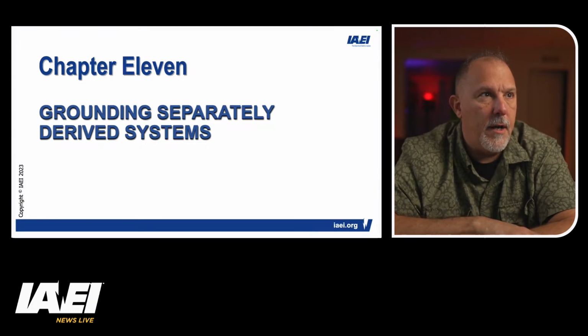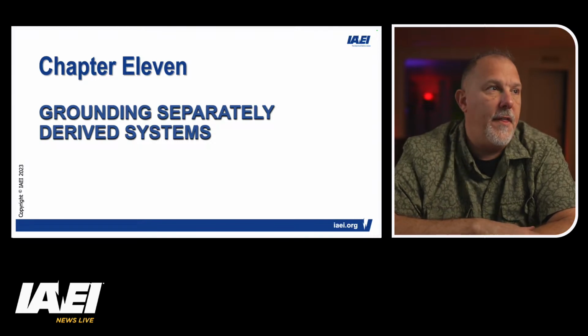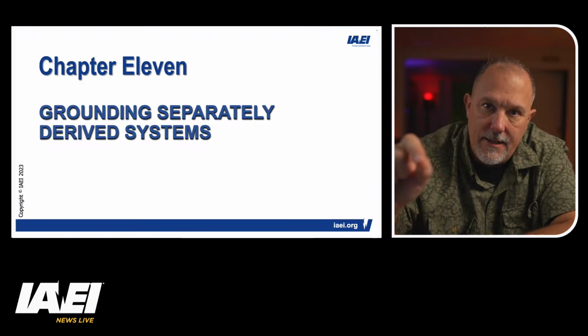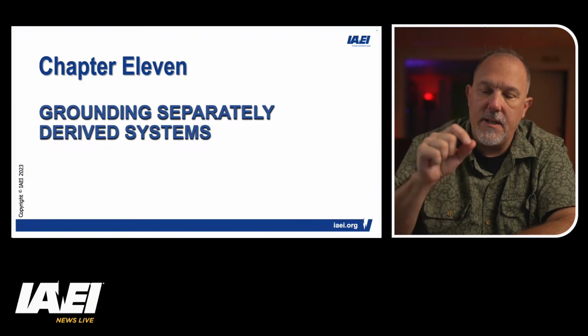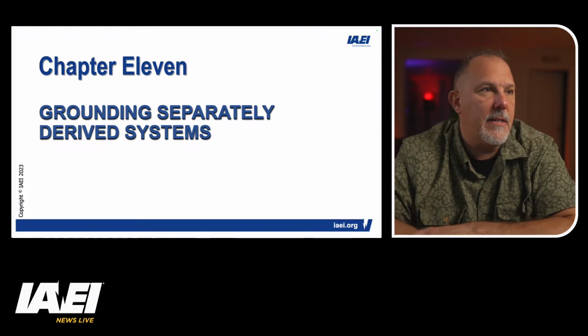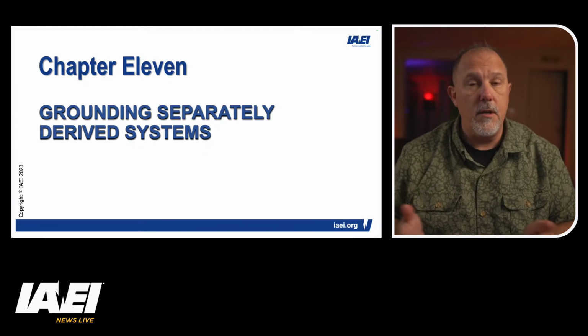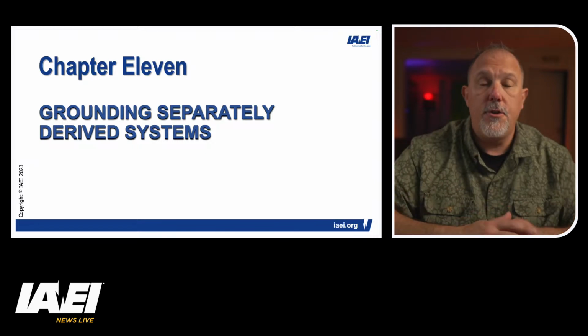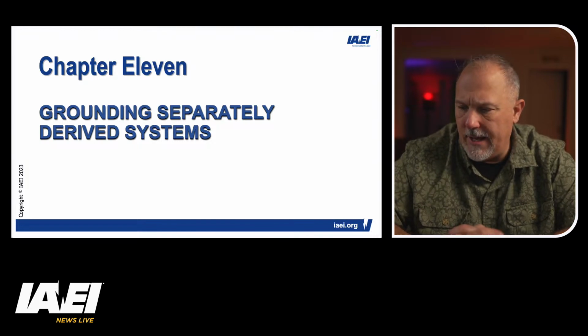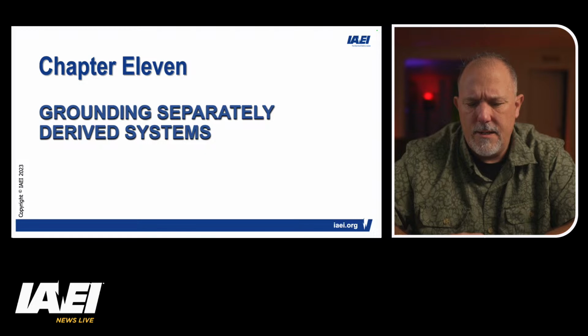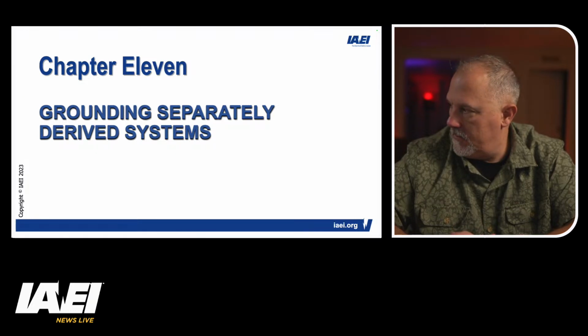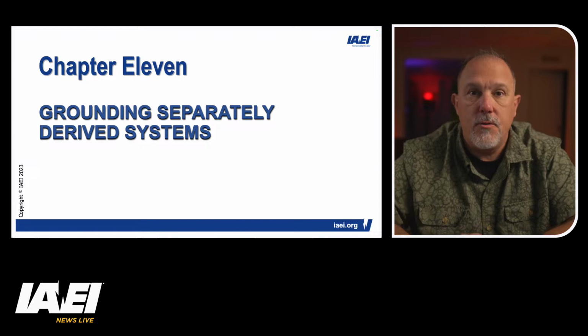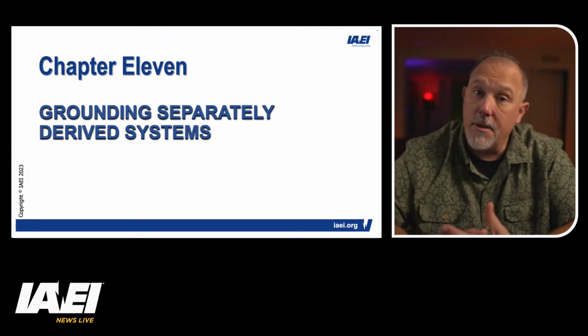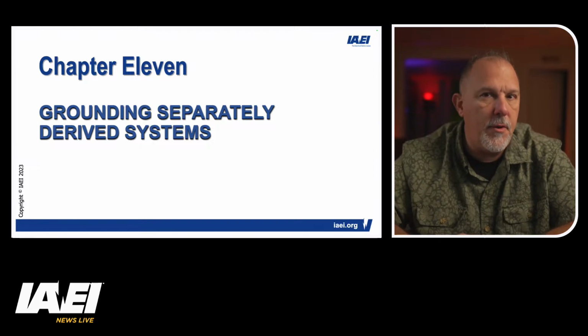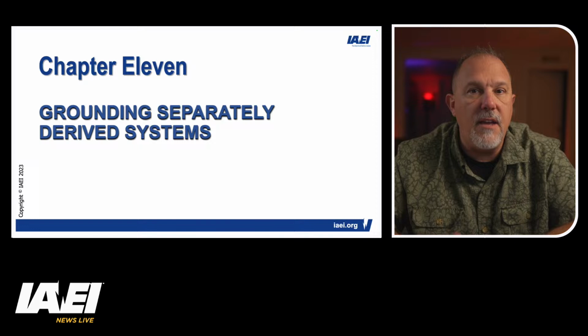You have a source. You're establishing a source. That source will have a capacity. You're going to have a specific capacity that is capable of being delivered. In the case of a transformer, we know we have the kVA of the transformer, and from the generator, you're going to have kVA from the generator. And in reality, the kVA of a transformer, I would argue, is not a cap. It's not like you can't get any more than that. Generators are only going to produce so much. A transformer, you can transmit more than its kVA rating.